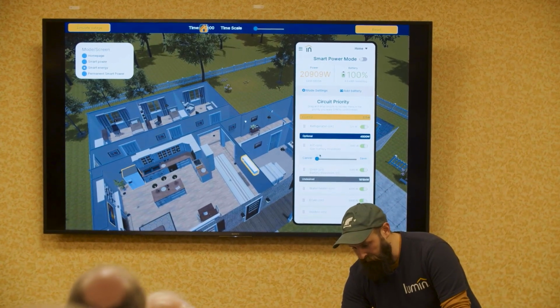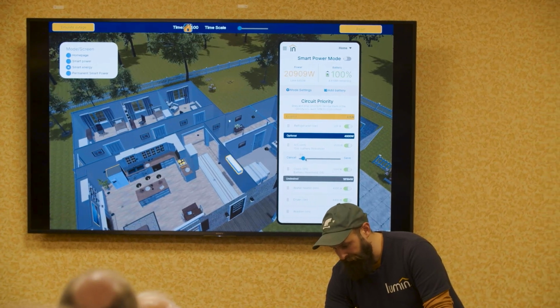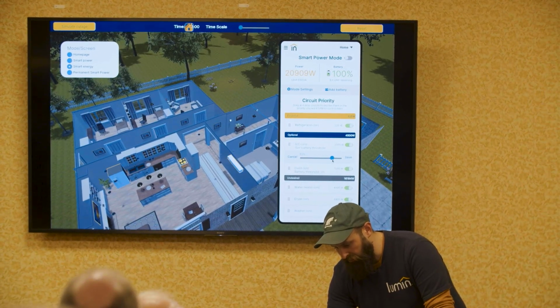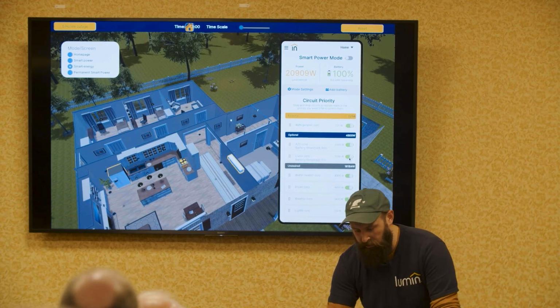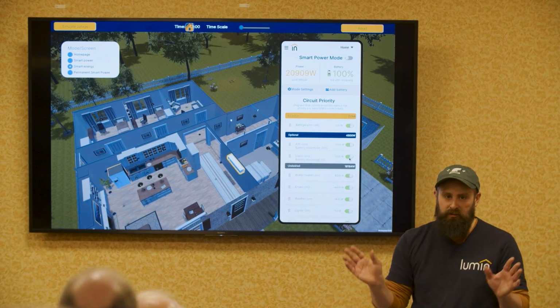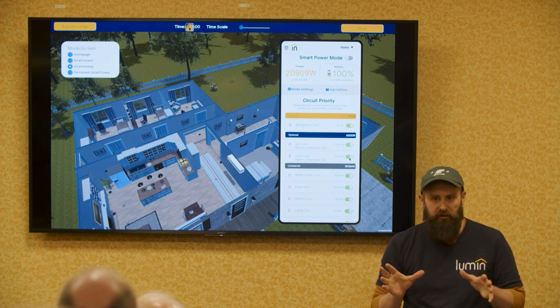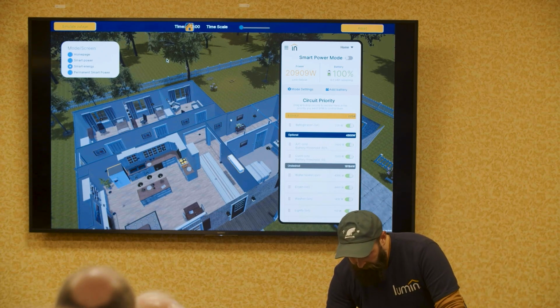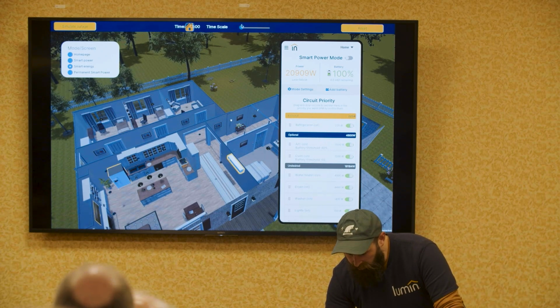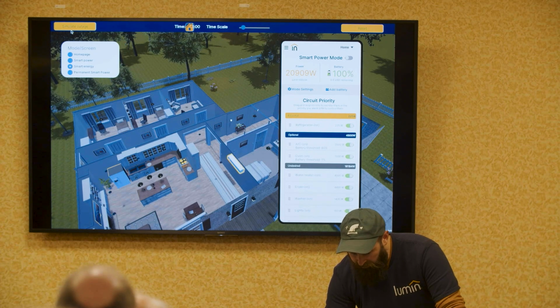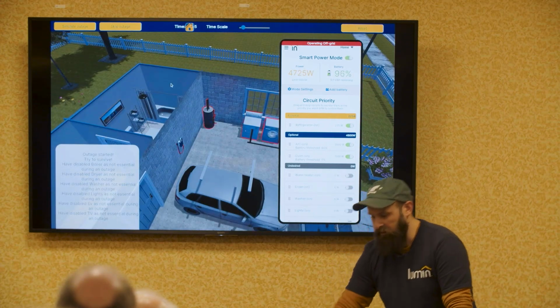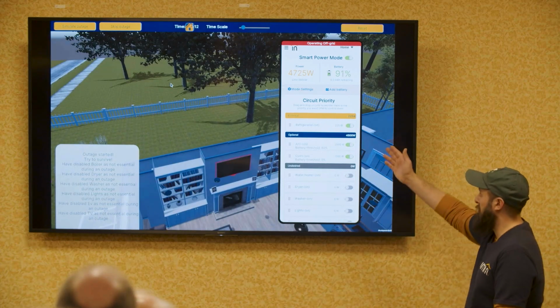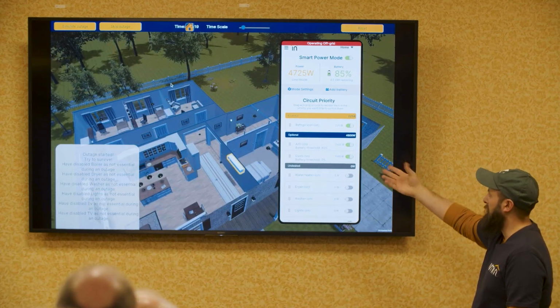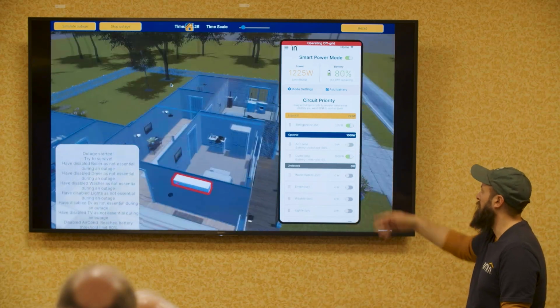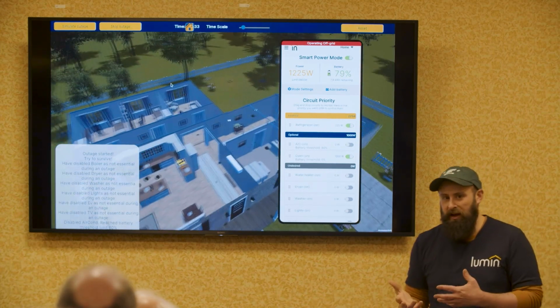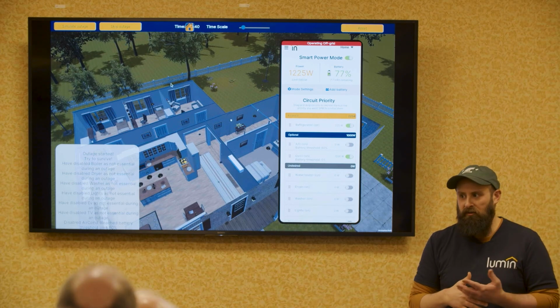So let's say we set this threshold to 80%. We want the AC to have the ability to run, but once the battery goes below 80%, we go into survival mode. If we simulate an outage, let me bump the timescale a little bit. So you can see the battery system using the battery capacity, and once we get to 80%, the AC will kick off. We can do that, but only with SolarEdge and Enphase.